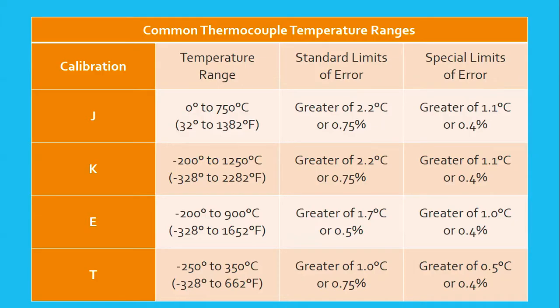Common thermocouple temperature ranges. Type J temperature range 0 degrees to 750 degrees Celsius. Standard limits of error: greater of 2.2 degrees Celsius or 0.75 percent. Special limits of error: greater of 1.1 degrees Celsius or 0.4 percent. Type K temperature range minus 200 degrees to 1250 degrees Celsius. Standard limits of error: greater of 2.2 degrees Celsius or 0.75 percent. Special limits of error: greater of 1.1 degrees Celsius or 0.4 percent.